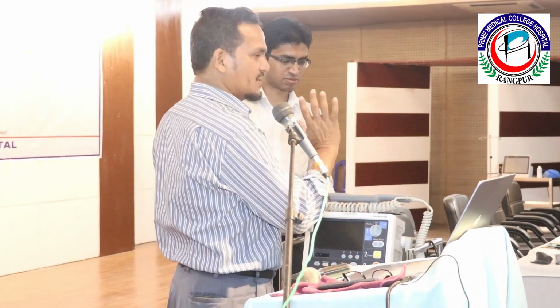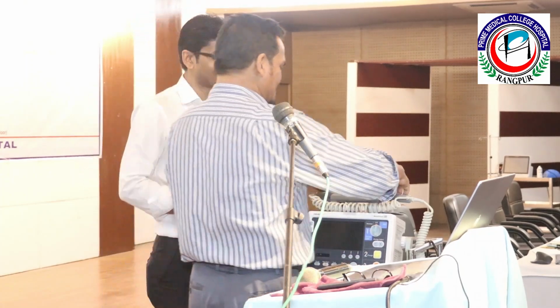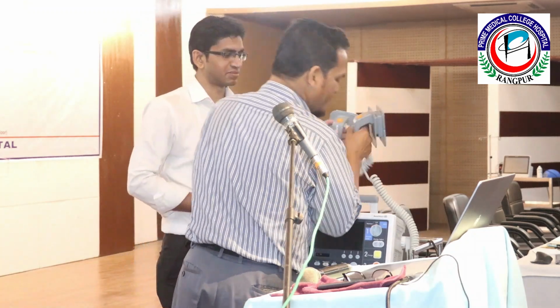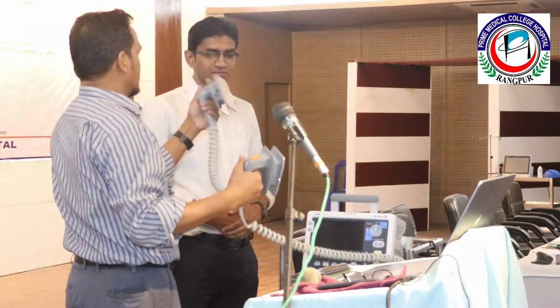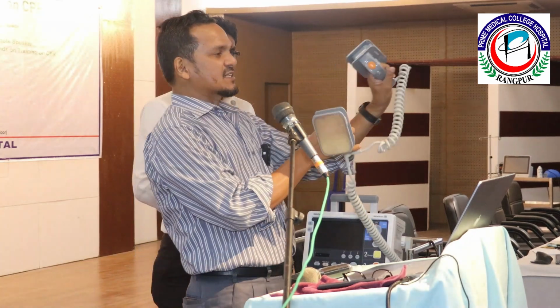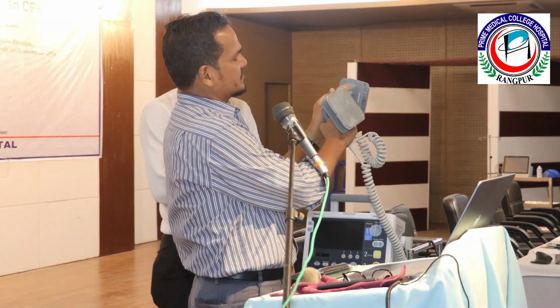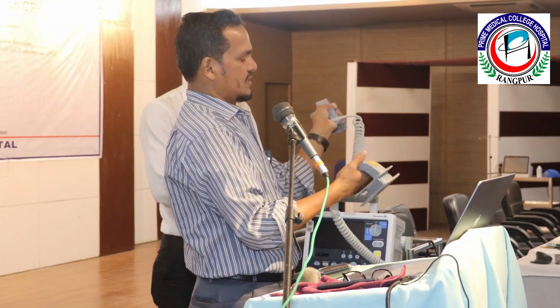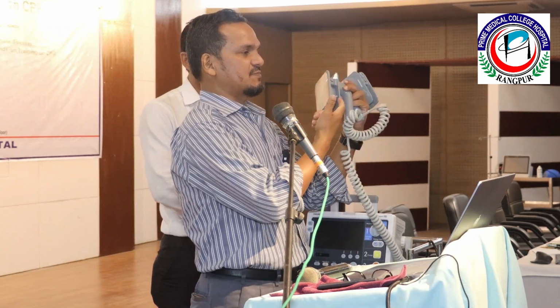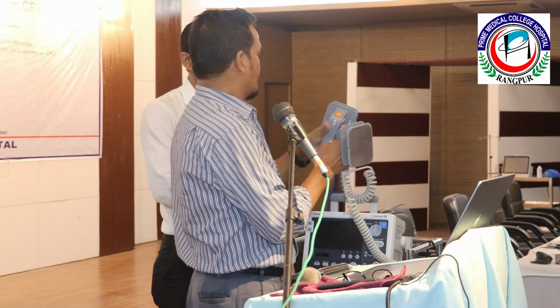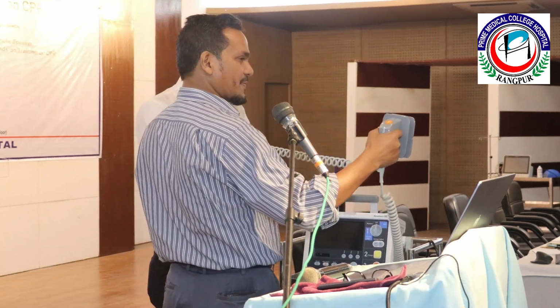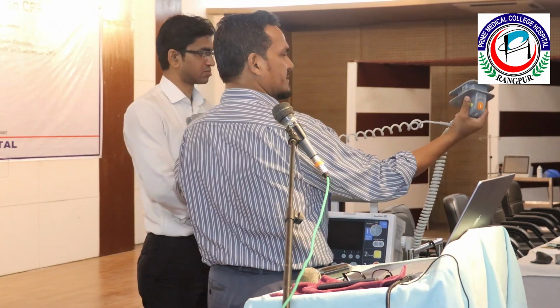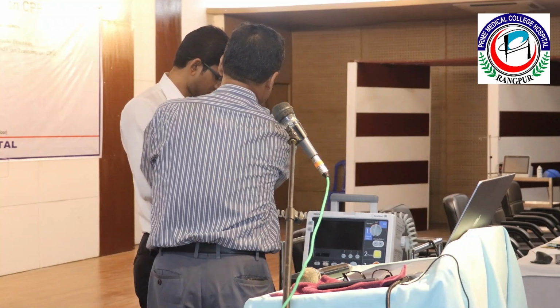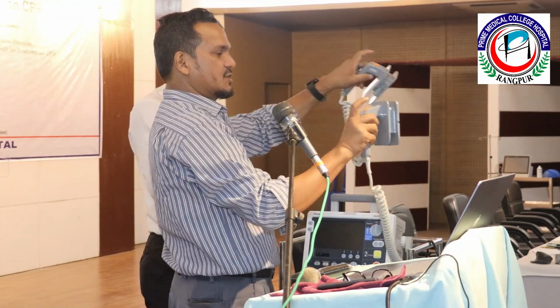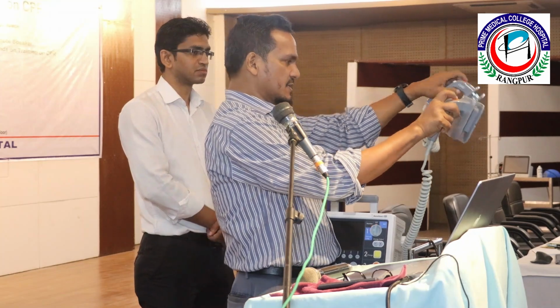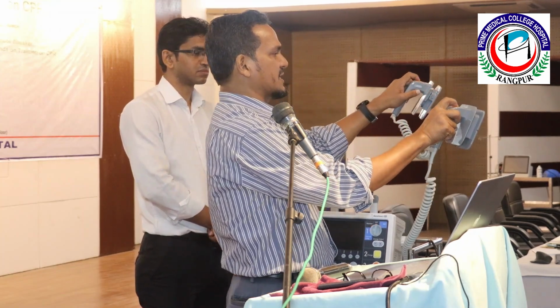Okay, we have got one live person here. To place the paddles, they are marked. This one is marked right, and this one is marked apex. Place the apex paddle over here, and this one here. And for the shock button, these two buttons should be pressed simultaneously.